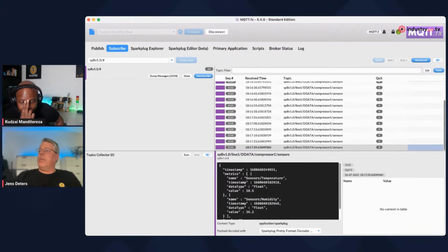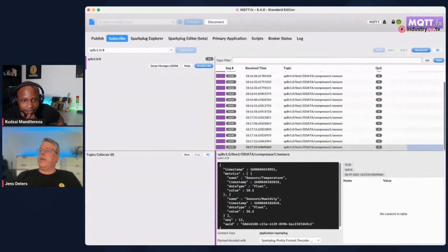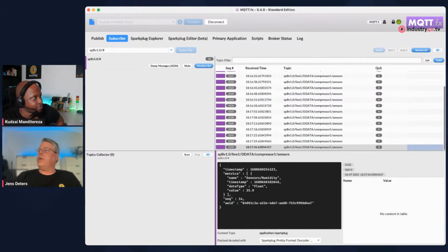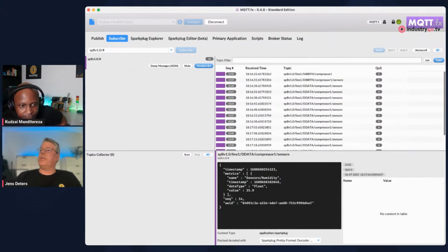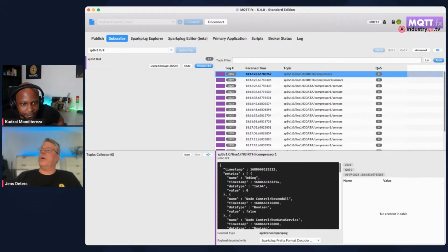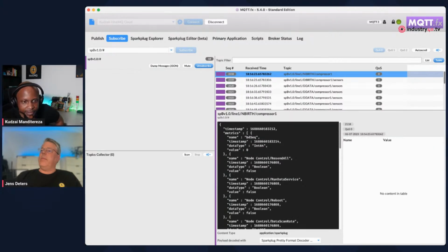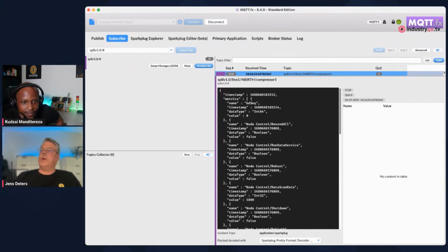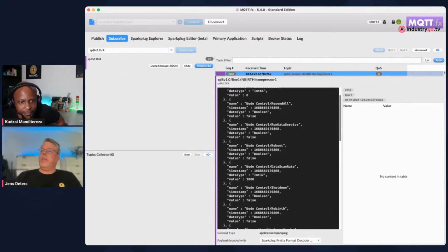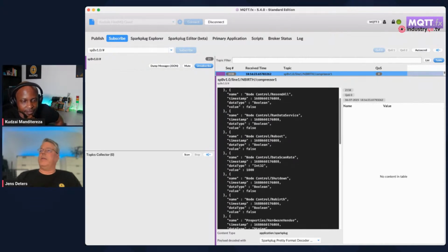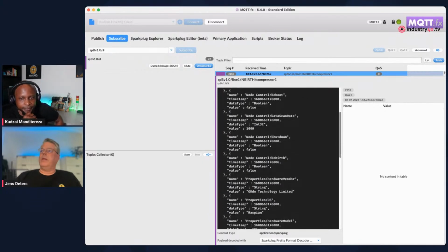So currently, messages are already arriving at MQTT.fx. So first of all, let's have a look at the first message that has been received. It's the node birth message for compressor 1. So line 1, compressor 1. Let's have a closer look. It's according to the specification. So there's a birth death sequence number, starts with value 0, followed by the commands that this device's edge of network node is able to handle.